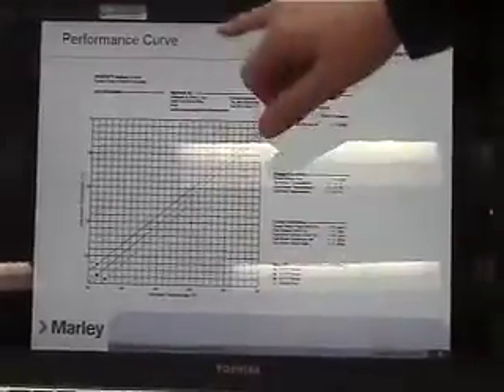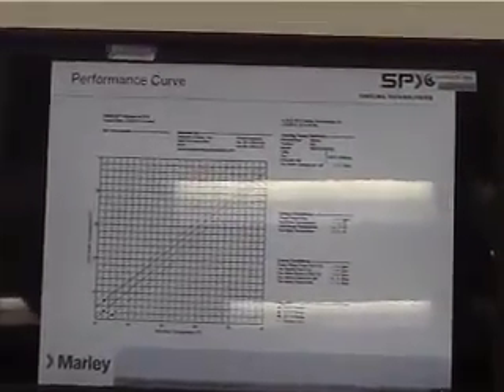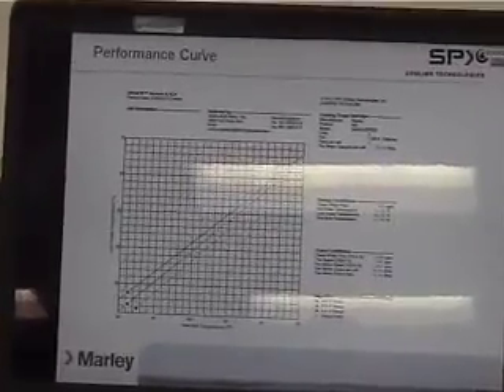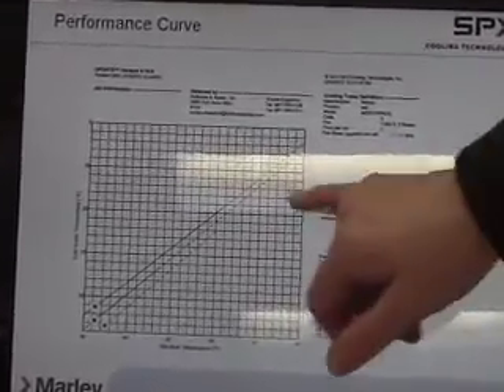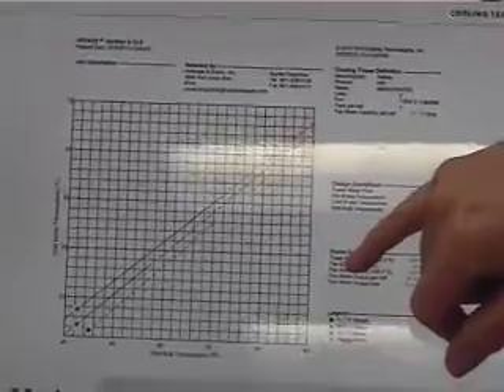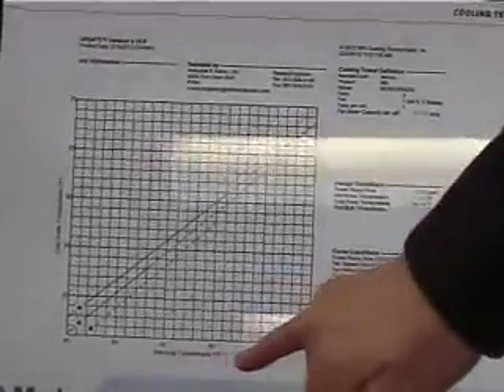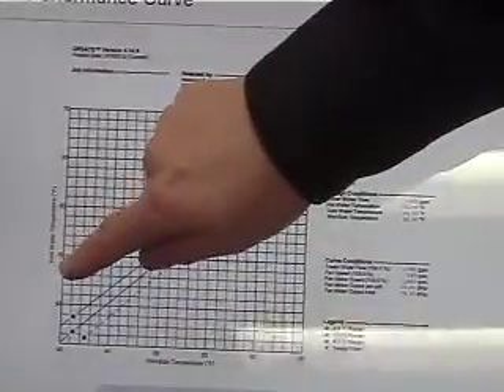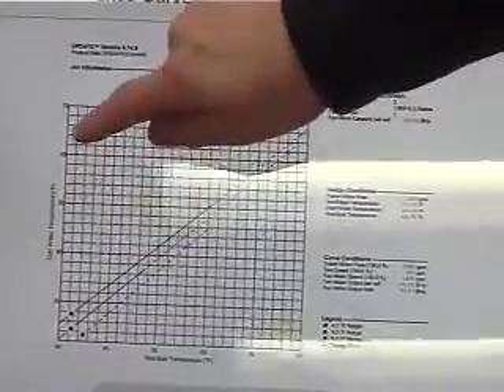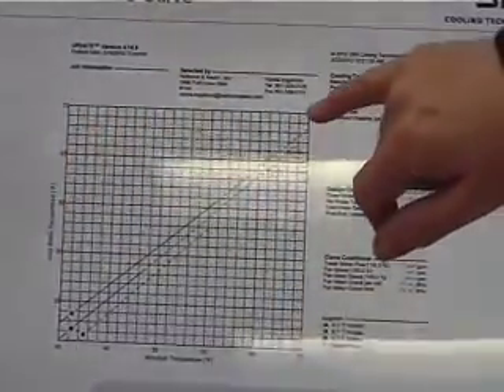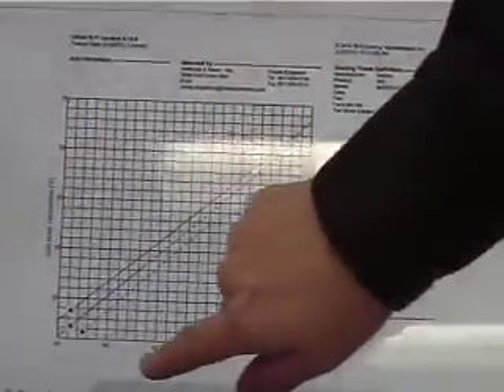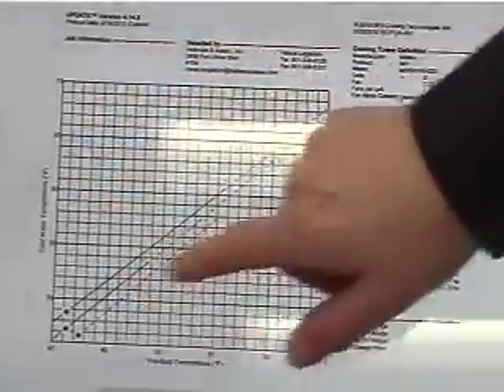This is your performance curve. Again, these are items that are required. This shows the wet bulb temperature along the bottom and the cold water temperature along the side. As the wet bulb temperature goes down, your cold water temperature can go down.